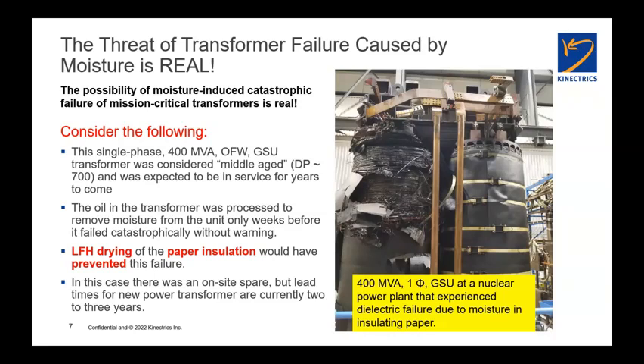And absolutely no question, as a result of the failure analysis, that this transformer failed, catastrophic dielectric breakdown due to moisture in the insulating paper. And what's really interesting from my perspective is that this transformer had just been, quote unquote, serviced by conventional oil processing only weeks before this failure happened.